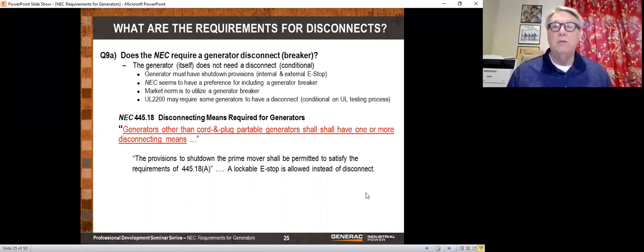Now, if you don't want a circuit breaker, then the generator must have shutdown provisions, which is an internal and an external e-stop. And you really need overcurrent protection out there. And so the NEC, as you read it, just assumes that a generator has a circuit breaker. And so we put one on there. But you could get away without it, and a lot of people do that.